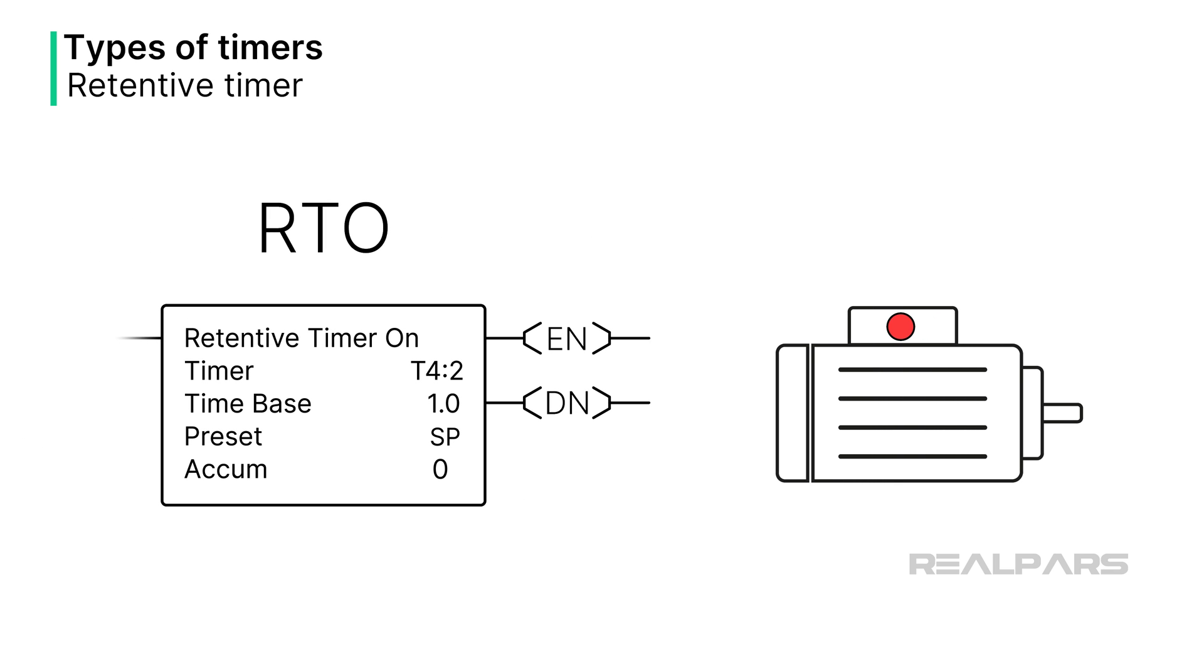A typical use of retentive timers is to track runtime on a piece of equipment, so that the optimal time for maintenance can be determined. In this case, the timer runs as long as the machine is running. Once the machine stops, the timer stops, but starts again once the machine starts back up. The retentive timer tracks total runtime, and once the preset has been reached, a maintenance flag is set, indicating it's time to change a roll of labels on a packing line for example.